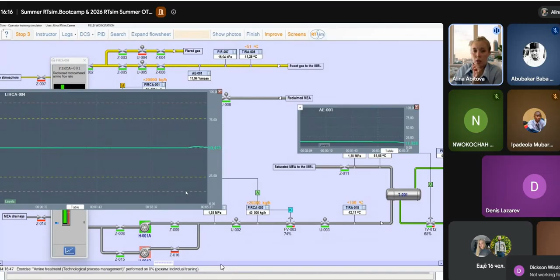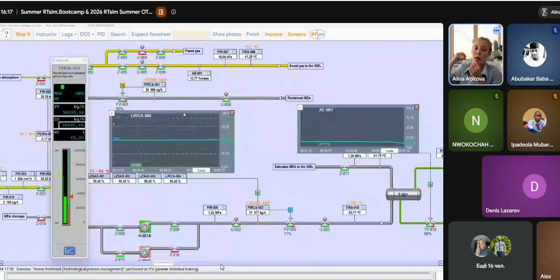So the level in the cube returned to 50% because the LIRCA4 device, in conjunction with the FIRCA3 device, in cascade control mode, leveled the level in the column. Because as you know, cascade mode works like hands and eyes: the level device monitors the level and gives the information to the control valve, which controls the situation in the column. So the cascade control mode leveled the level in the column.